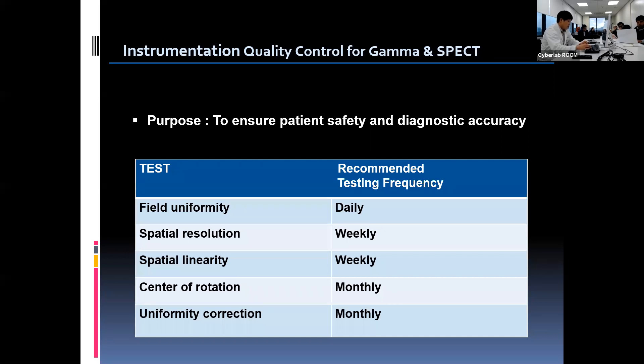Let's look at the table. Field uniformity is done daily, and spatial resolution and linearity are tested weekly, and center of rotation and uniformity correction are done monthly. However, testing frequency can vary depending on the manufacturer's recommendation or institution policy. Because of the improvement of technology in clinical imaging equipment, test frequency can be reduced.